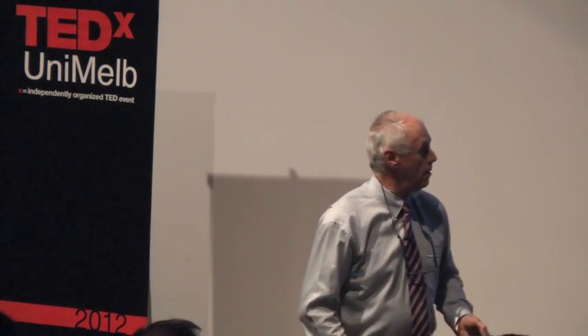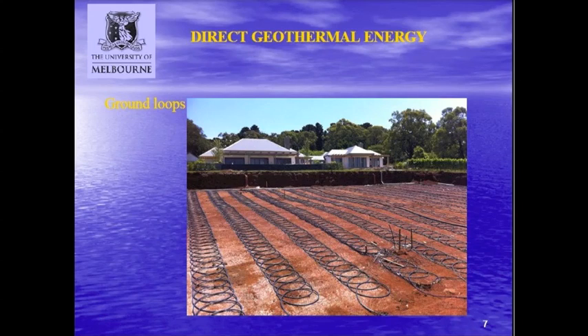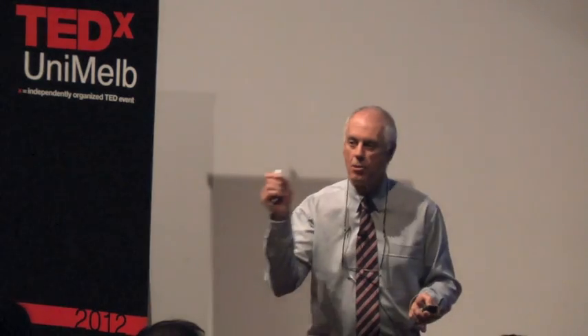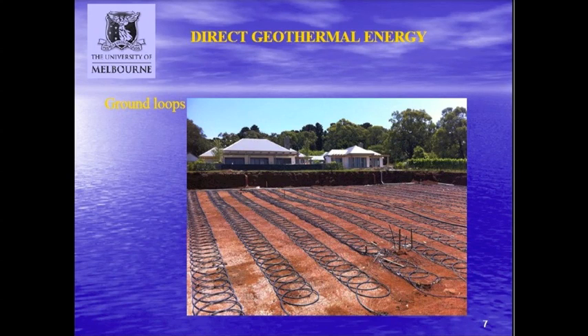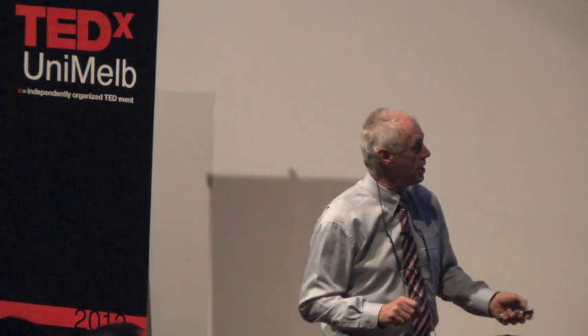The Walter Boas ground floor will have geothermal energy heating and cooling fairly soon. Of course, that's going vertically, and it does get quite expensive. Sometimes if you've got the space, it's a lot better to do it horizontally. It's not as efficient, because at two metres deep the ground temperature will vary a bit - in this location at Main Ridge on the Peninsula, maybe between thirteen and seventeen degrees - but it's a lot cheaper. Drilling is very expensive. This is a large house, about eight times the size of an average house, using what's known as a slinky system. These are a set of loops set up as part of an observation and test field.